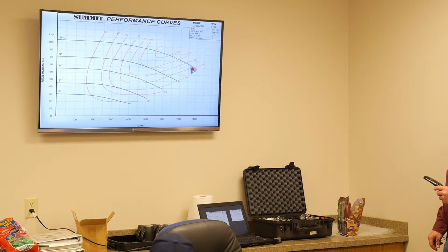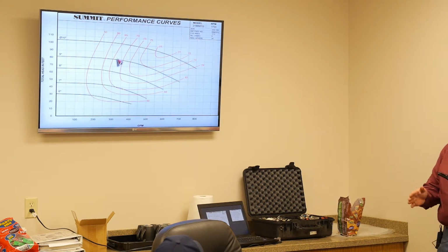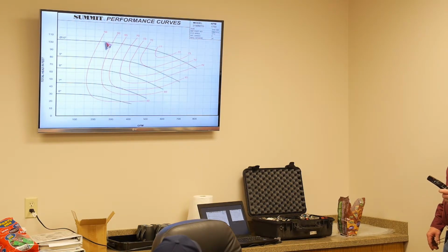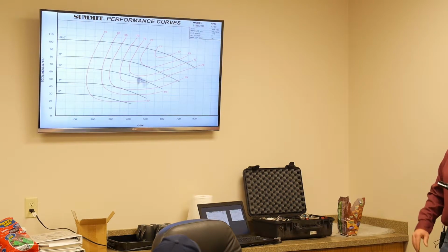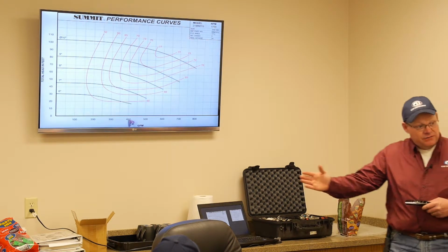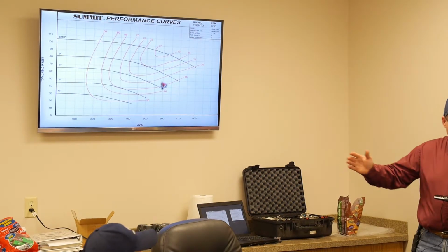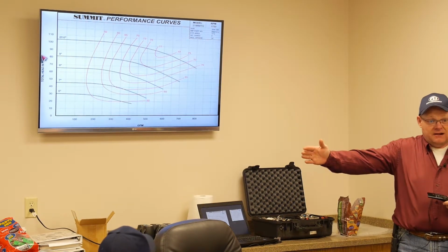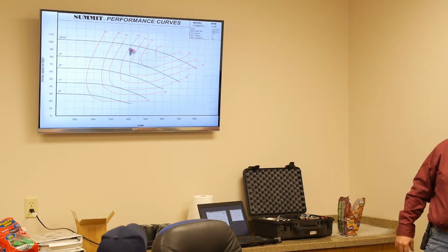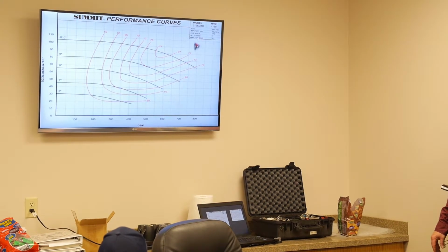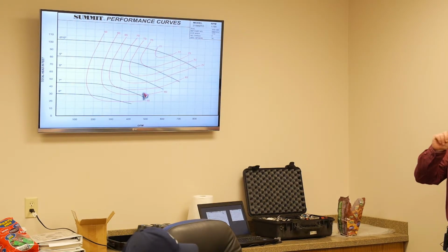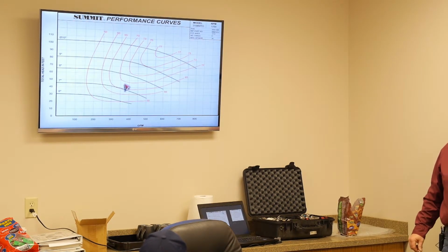So same principle. If we're starting to run out here and we're about to fall off the curve, what's happening? We're getting shaft deflection the other way because we're running against the cutwater, right? The other thing is that when you're running over here, you're getting some axial play. Not a lot, but when you're over here, that impeller is trying to suck right through the front of that pump. When you don't have enough back pressure to keep it on the curve, that impeller is trying to run right out through the front, and that seal face is opening up. Does that make sense? So what I'm trying to get to ultimately is that short amounts of pressure change affect the internals of the pump hugely, quickly. Okay?